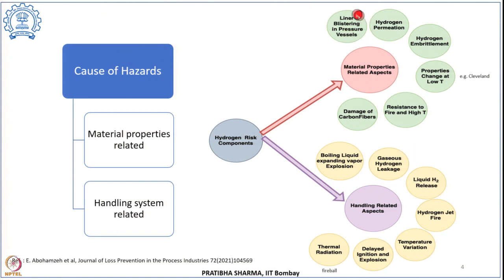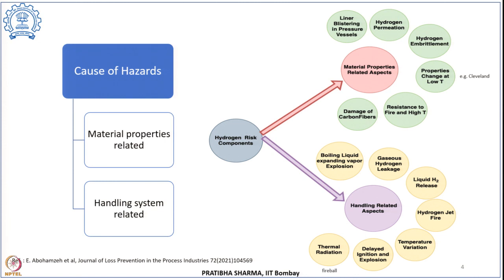Another important material property related hazard is liner blistering in pressure vessels. In type 4 vessels — which have an overwrap of carbon fiber composite and an inner polymer liner — when hydrogen is filled at high pressure, a certain amount of hydrogen gets absorbed into the inner polymer. If the depressurization rate is greater than the rate at which hydrogen escapes by diffusion during depressurization, there could be delamination or blistering of the polymer liner. This blistering depends upon parameters like initial filling pressure, discharge rate, and dwell time.